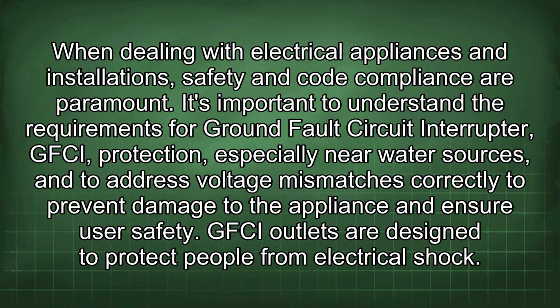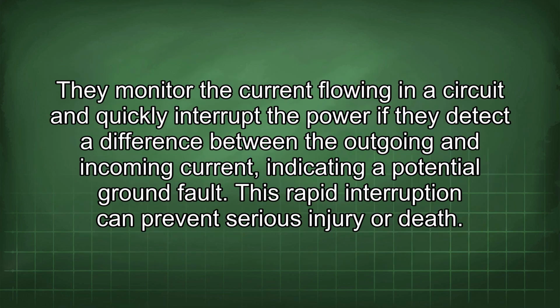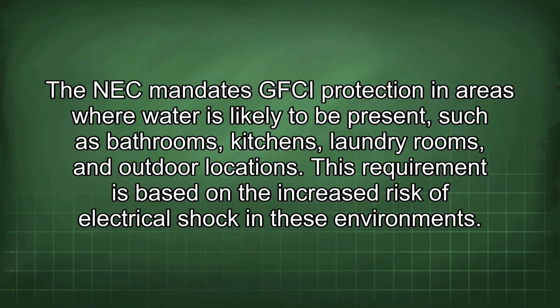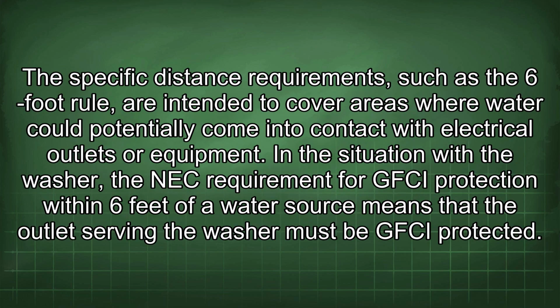GFCI outlets are designed to protect people from electrical shock. They monitor the current flowing in a circuit and quickly interrupt the power if they detect a difference between the outgoing and incoming current, indicating a potential ground fault. This rapid interruption can prevent serious injury or death. The NEC mandates GFCI protection in areas where water is likely to be present, such as bathrooms, kitchens, laundry rooms, and outdoor locations. This requirement is based on the increased risk of electrical shock in these environments. The specific distance requirements, such as the 6-foot rule, are intended to cover areas where water could potentially come into contact with electrical outlets or equipment.